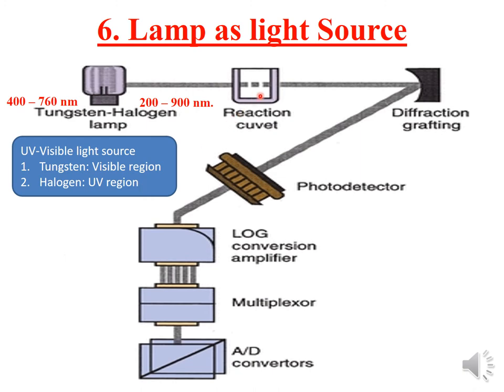This is the reaction cuvette, and this is the diffraction grating system. This is how the photodetector measures absorbance and converts it into a reading after calculations.